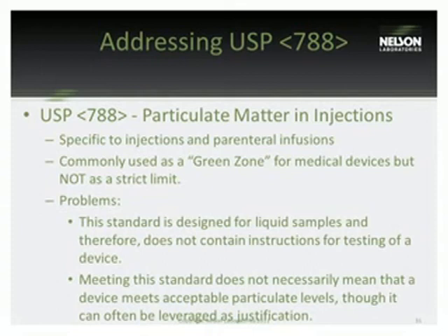The standard is designed only for liquid samples, and therefore it doesn't contain any instructions, no procedural details as to how to test the device. In addition, the FDA has often mandated that meeting this standard, even if your counts are below the 788, does not necessarily mean that a device has acceptable particulate levels, though it usually can be leveraged as justification. It's not difficult to use the 788 as some sort of justification that if a solution has X amount of particles and the device has less than that, it should be safe. But it's still not a good idea to depend on that justification on its own for approval from any regulatory agency, maybe as some type of backup or a scientific rationale, but not on its own.